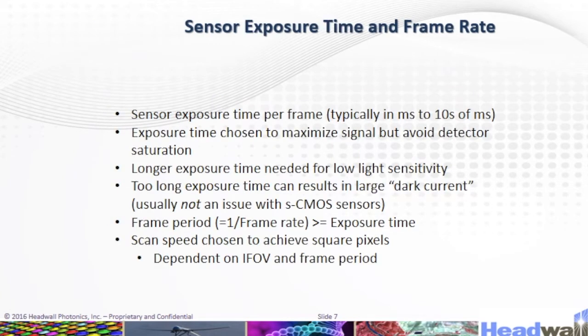Here is the sensor exposure time and frame rate. Sensor exposure time per frame is typically in milliseconds to tens of milliseconds. Exposure time is chosen to maximize signal but avoid detector saturation. Longer exposure time is needed for low-light sensitivity, but too long an exposure time can result in large dark current — usually not an issue with sCMOS sensors. Scan speed is chosen to achieve square pixels depending on IFOV and frame period.